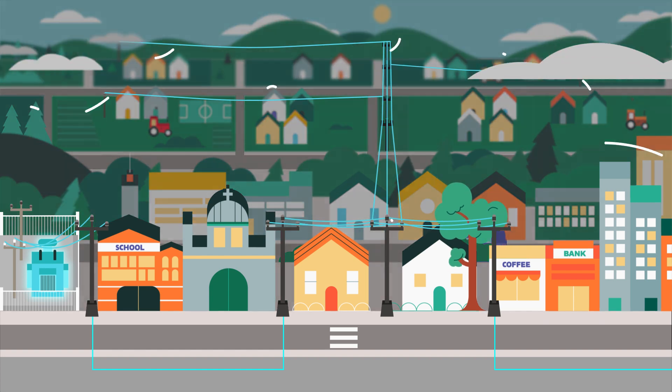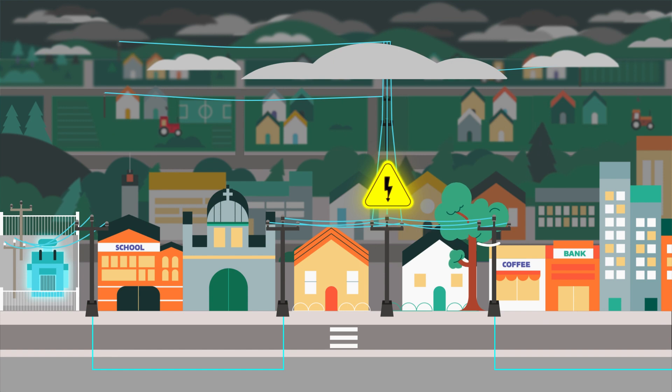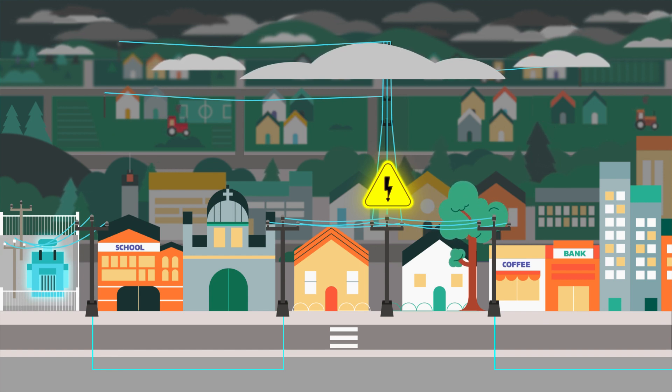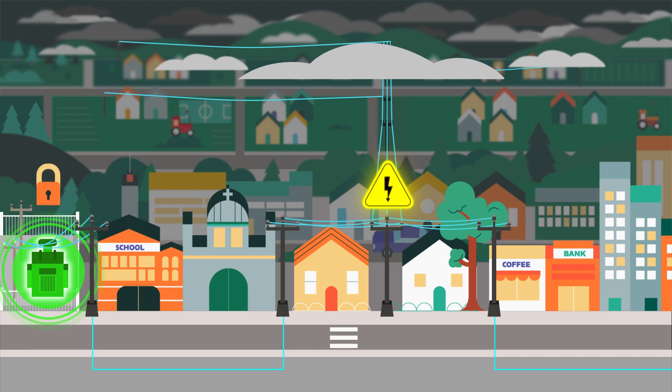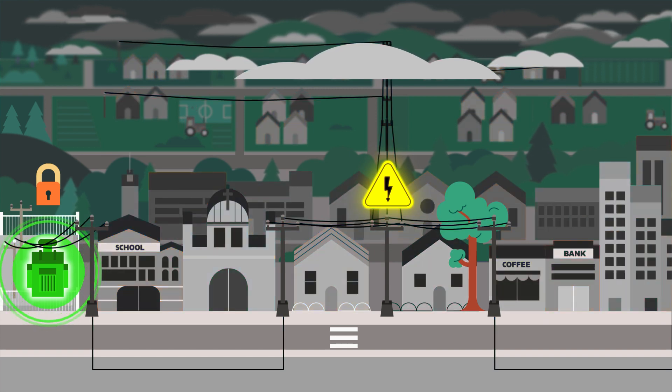Instead, many utilities use a one-shot-to-lockout approach when there's a fault on a circuit with underground lines. Using this method, the substation circuit breaker opens and locks out immediately after detecting fault current. No fault testing is involved.